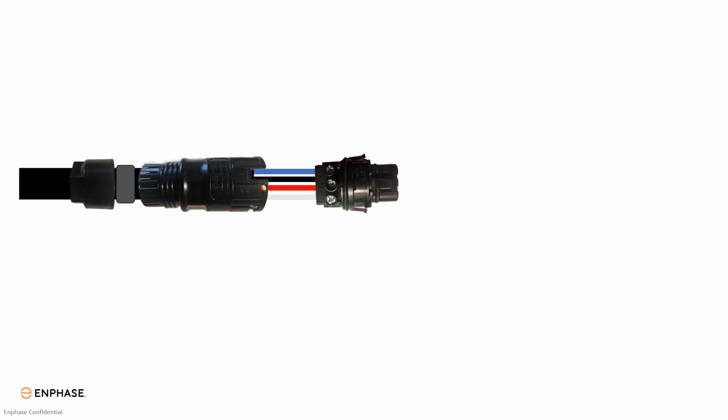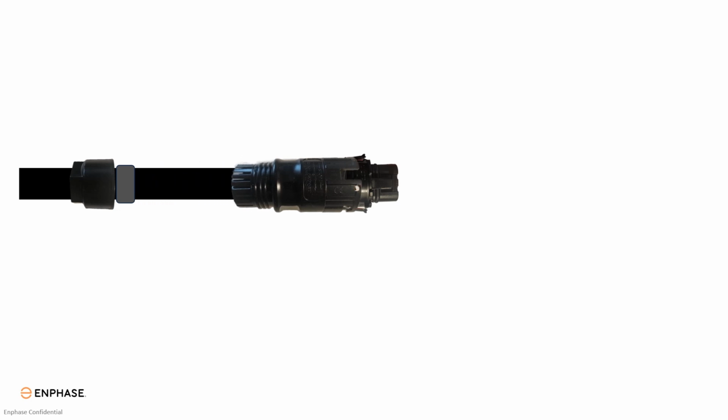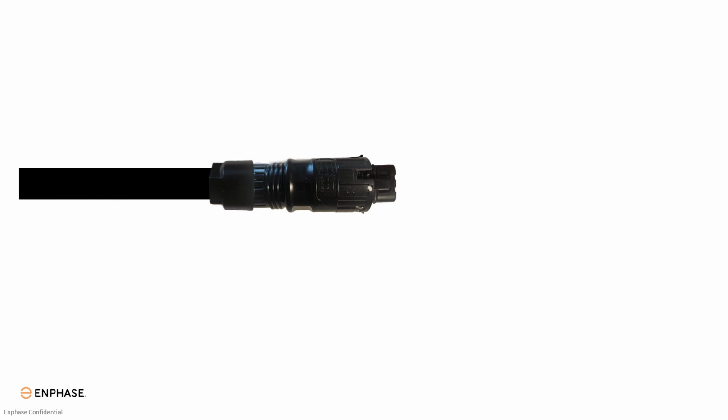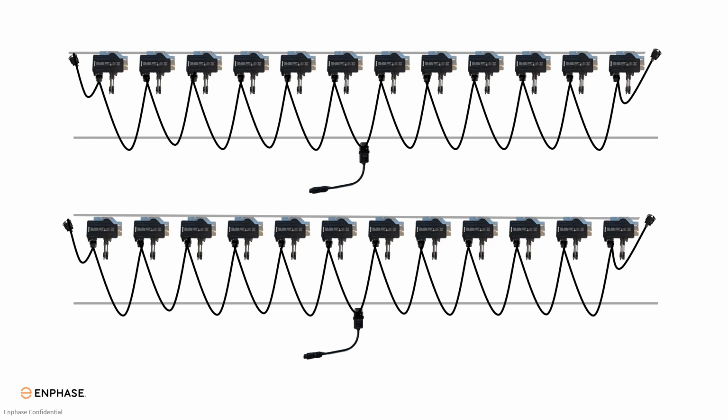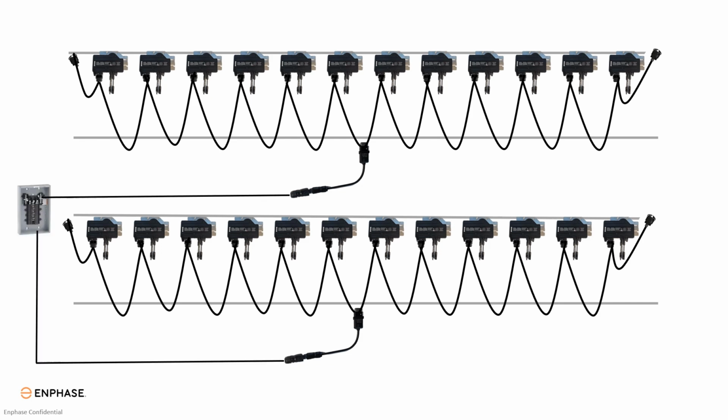Next, slide the housing up onto the contact carrier until you hear a click. Then slide up the seal. And lastly, slide up the cable gland and tighten the cable gland on the housing to 39.8 inch pounds. Once we have our male field wireable installed on the raw QD cable, we can plug them into our center tap adapters. We will follow those steps for each circuit that we have. Now we can run those home runs back to either a combiner panel or junction box.